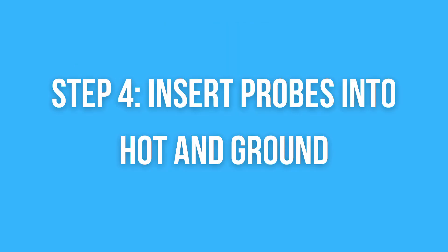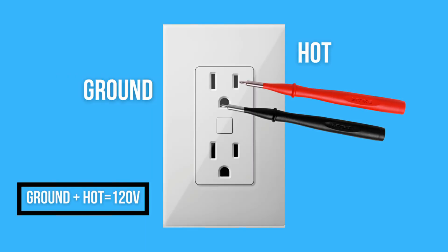Now connect the probes to the hot and ground. The result you need to get is the same as with neutral and hot. This means that the multimeter should show between 110V and 130V. Also, less and more voltage than that is a sign that the ground is incorrect.